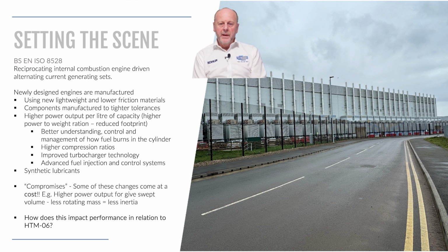So we also add to that a better understanding of control and management of how the fuel burns in the cylinder, higher compression ratios, improved turbocharger technology, advanced fuel injection and control systems, many new innovations. But some of these innovations, which are focused on the reduction of the consumption of fuel and the emission of CO2, for example, come with compromises. So there is a cost. So, for example, this higher power to weight ratio, or per swept volume, means that there's less rotating mass in the generating set itself, so there's less inertia.